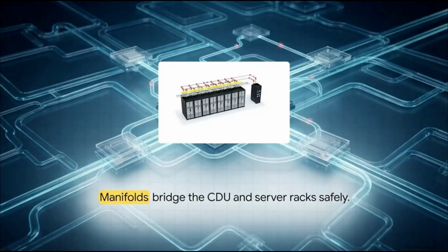Notice how these heavy-duty row-based manifolds bridge the gap between the CDU and the dense server racks. Because we're pumping pressurized liquid over incredibly expensive electronics, these manifolds are completely prefabricated and pressure-tested long before they ever arrive on site. Plus, the entire system is embedded with IoT leak detection sensors, keeping this high-density liquid infrastructure incredibly safe and stable.